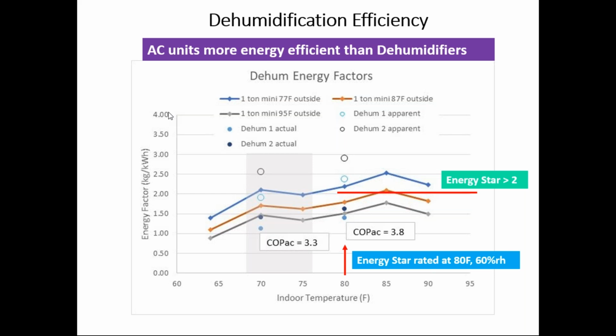But these two dehumidifiers, the two open circles, operate quite high, about 2.5 to 3 kilograms per kilowatt hour of operation. And that's in comparison to where we used to be, which was around 1 to 1.5, or where non-Energy Star, like cheap basement dehumidifiers, would be operating.